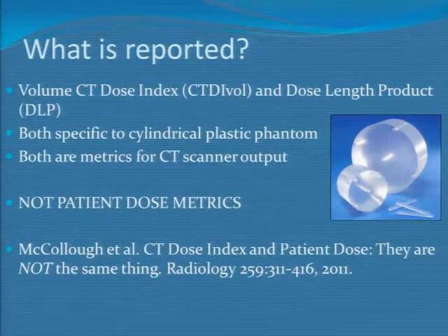So John has done a very nice job of explaining CTDI vol and dose length product, and the fact that they're both very specific to cylindrical plastic phantoms. They're really good metrics for scanner output. They're really lousy at describing patient dose.